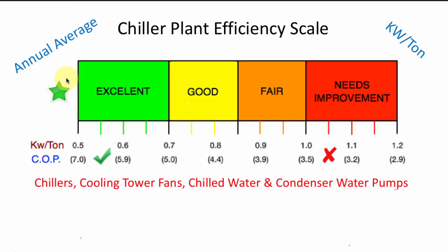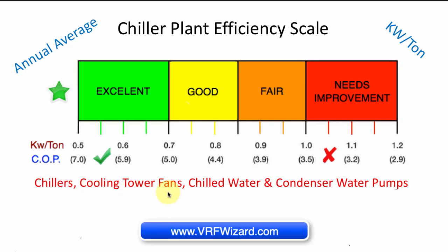If we look at a central plant, you would rate it by adding up your chillers, your cooling tower fans, and your chilled water and condenser water pumps — all the major power-consuming equipment in the central plant. When you do the KW per ton and COP calculations and add those together before calculating, you can see where your central plant falls. If you're falling in the red zone, there are efficiency improvements you can make. Simply add all the BTUs together, add all the KWs together, convert into BTUs per hour, and do the calculation the same way we did for the individual chiller.